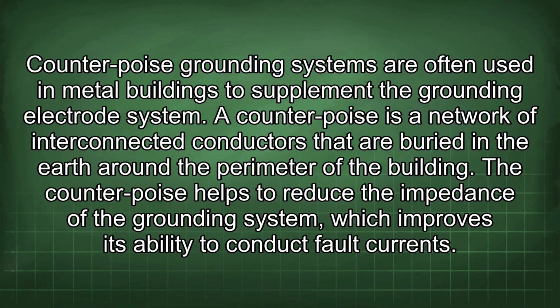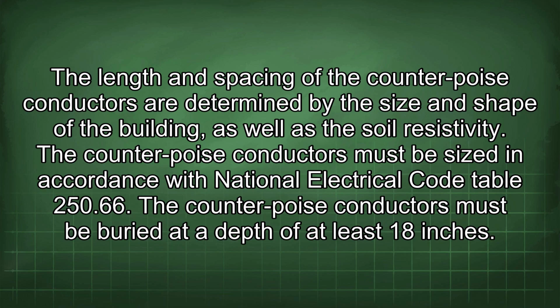Counterpoise grounding systems are often used in metal buildings to supplement the grounding electrode system. A counterpoise is a network of interconnected conductors that are buried in the earth around the perimeter of the building. The counterpoise helps to reduce the impedance of the grounding system, which improves its ability to conduct fault currents. The length and spacing of the counterpoise conductors are determined by the size and shape of the building, as well as the soil resistivity.